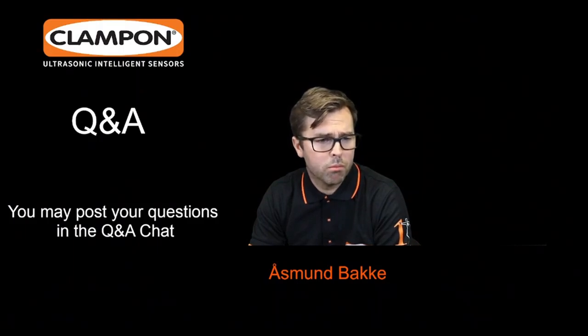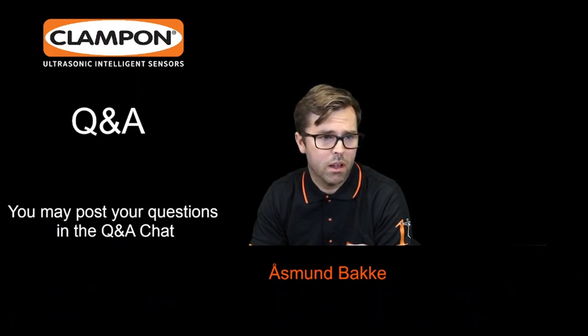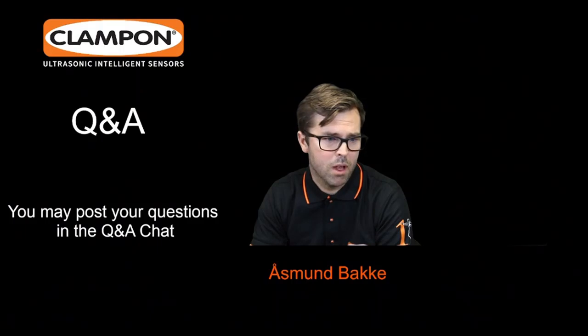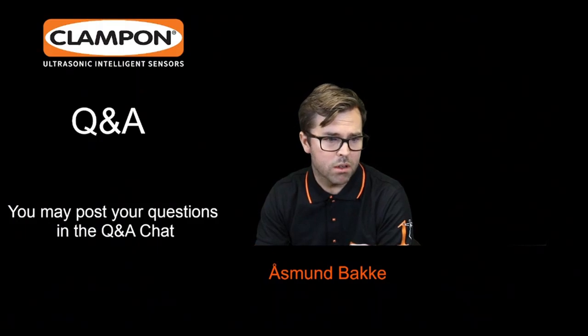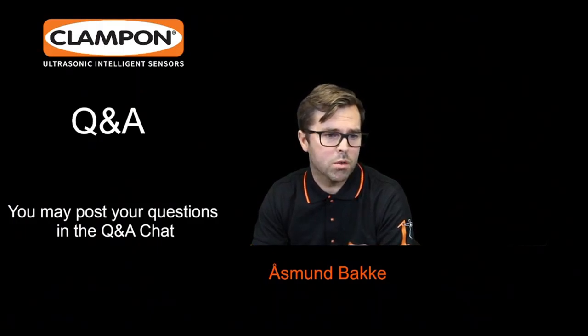When it comes to permanent systems, we have, of course, an issue with cyber security, because our system is also an alarm for the control room. We have to be careful with where the data can be stored and where it's transferred and what can be interfered with by others. So for permanently installed systems, the cloud solutions are not there yet, and maybe it can never come with regard to the alarm to the control system. But it's also possible to have that part of the system separated and then share the data out to a cloud, so it can be available for a virtual meter, etc.